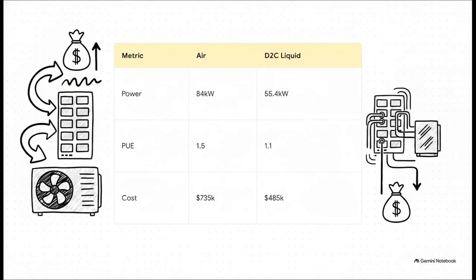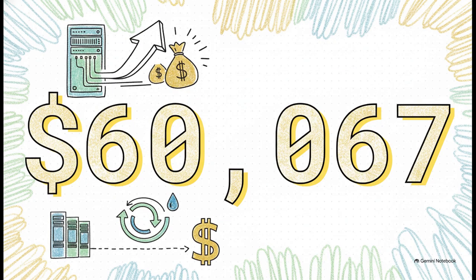Because at the end of the day, thermodynamics has to make financial sense, right? Let's talk about the cost comparison for a server rack filled with 8 of those intense 8 GPU systems we mentioned. With traditional air cooling, you need a whopping 84,000 watts of power per rack, mostly because of the massive air conditioning overhead. That gives you a power usage efficiency, or PUE, of about 1.5. But with direct-to-chip liquid cooling, because you're eliminating those internal fans and room air conditioners, the power needed drops to just over 55,000 watts. That tightens your PUE down to a hyper-efficient 1.1. So, in just 1 year, your total kilowatt-hour cost plummets from roughly $735,000 to about $485,000. Honestly, I couldn't believe this number when I first saw it.